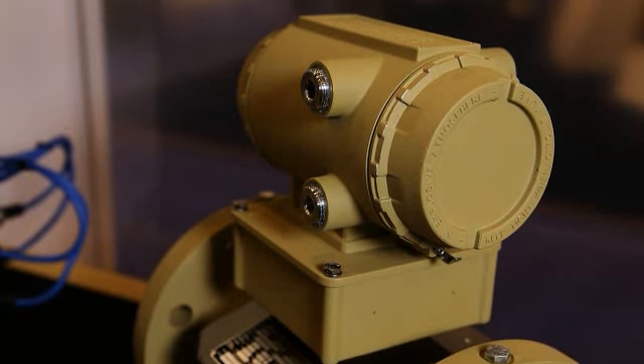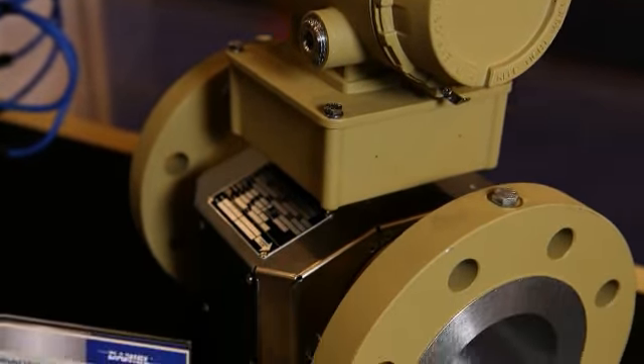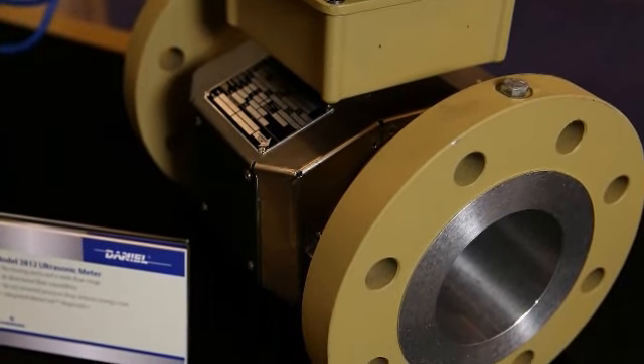Okay. Another way in which the ultrasonic meter can save operational costs is given the fact there is no incremental pressure drop from this device. So no extra pressure drop means reduced pumping costs for operators. If we go back to the example of the PD meter, in that example of 3,500 barrels per hour going through a 10-inch PD meter, that was generating an incremental 4 psi of pressure drop in the system. With that same process going through the 6-inch 3812, we were generating an incremental 0.4 psi. So that reduced incremental pressure drop means smaller pumps, means less pumping costs, and again contributes towards the overall operational cost savings of the product.